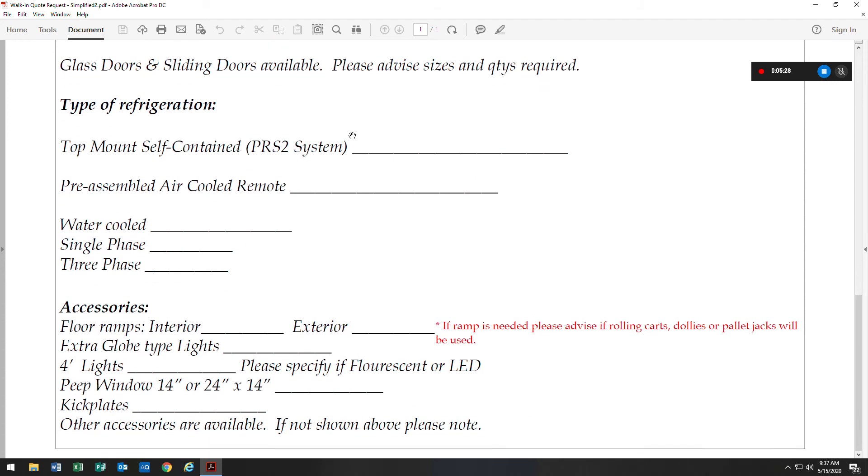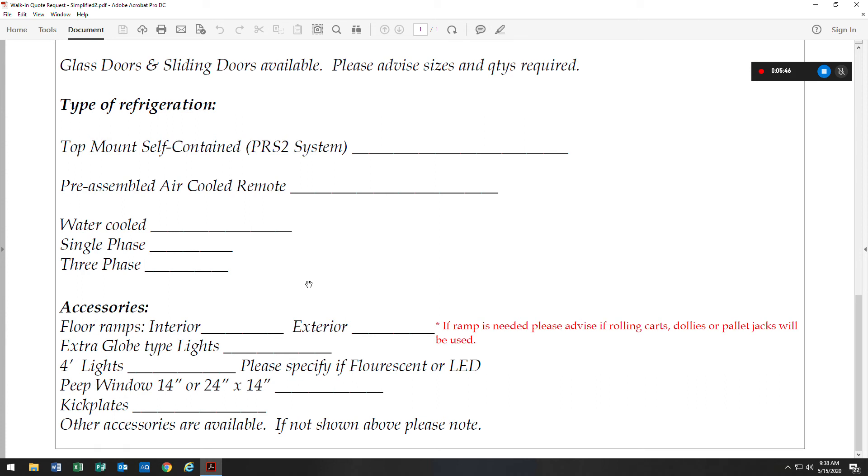We have different types of refrigeration. We have a top-mount self-contained and we also have a pre-assembled air-cooled remote and water-cooled available in single-phase or three-phase. Not all top-mount self-contained systems are available in three-phase, so that would need to be determined at the time of the quote.